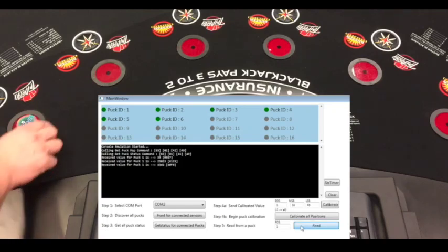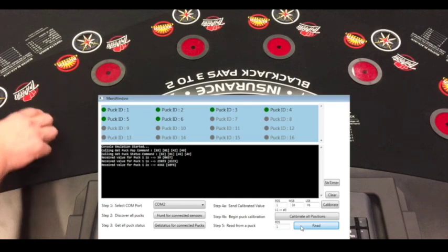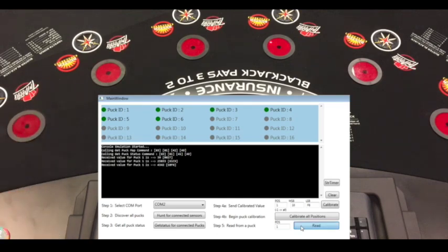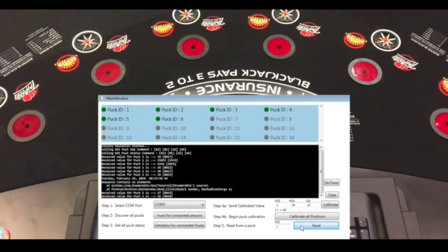So when we're calibrating, we want to make sure that the number we calibrate with isn't extremely high or way higher than the number that the chip gives us. And the reason I just showed this little test here is so you see what these numbers are doing and what numbers the different things covering the sensors give you. We can also just hit read a bunch of times and get a whole bunch of different readings out of it. Now, when you see "the sequence contains no elements," all that means is we were calling out to the sensor too fast and it wasn't able to give us a signal.